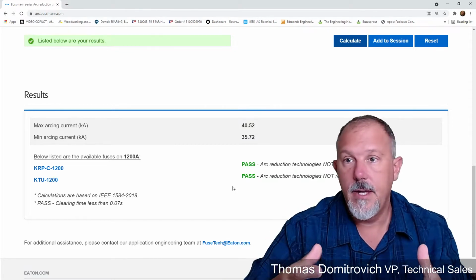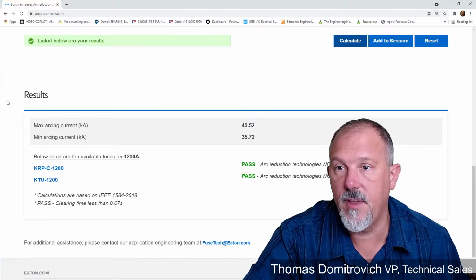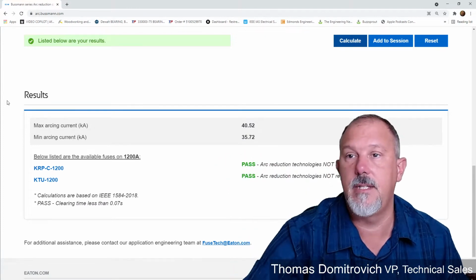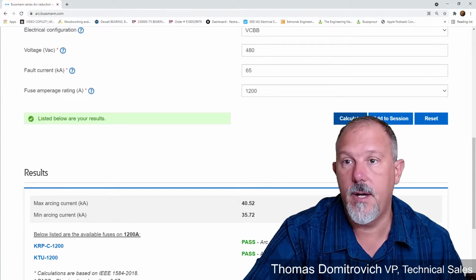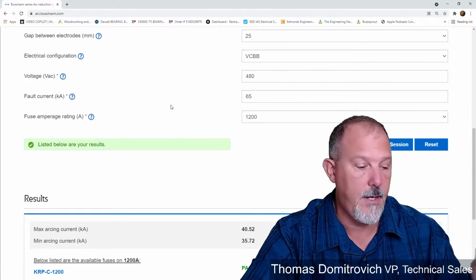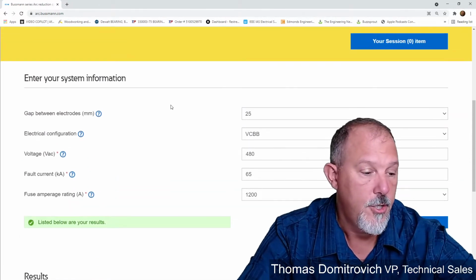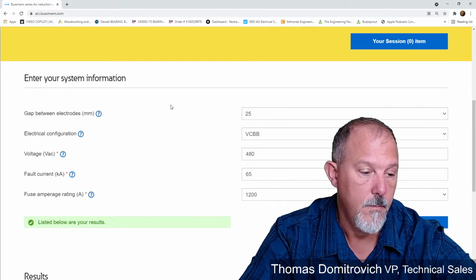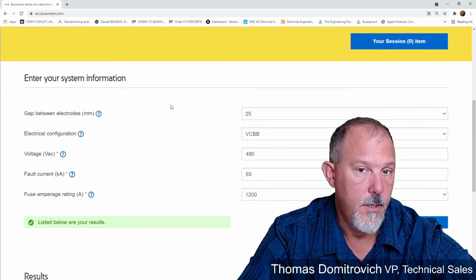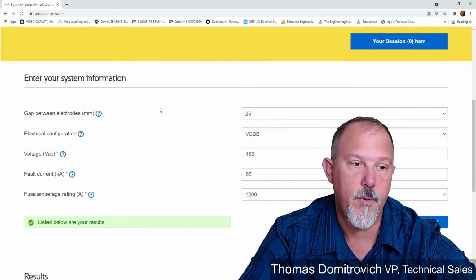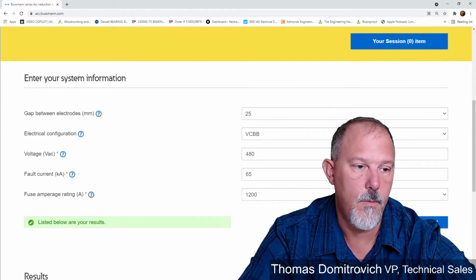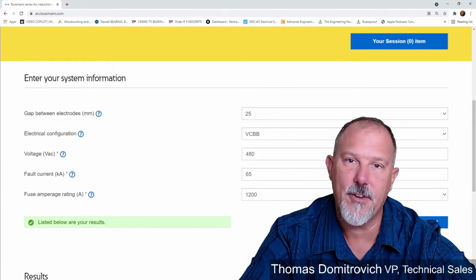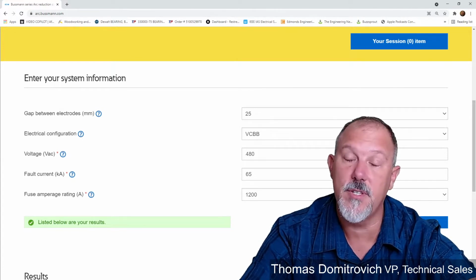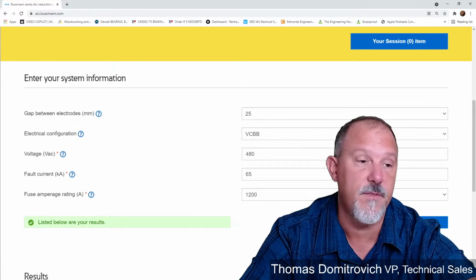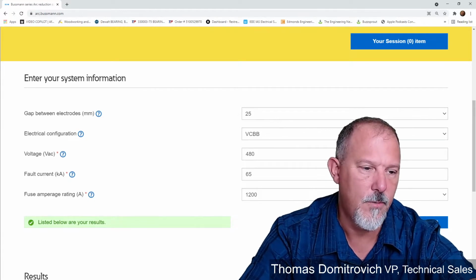So hopefully, to your point, JW, this might help those in the trade and in the industry, and inspectors, to come up with an evaluation and calculate arcing currents. All you have to be able to do is come up with that minimum bolted fault current value.